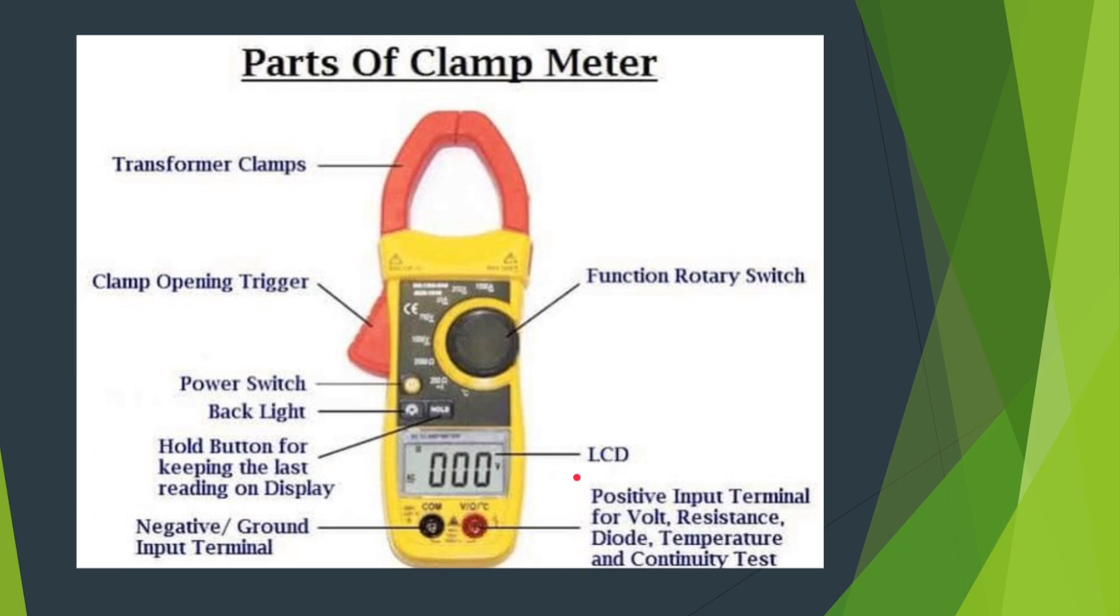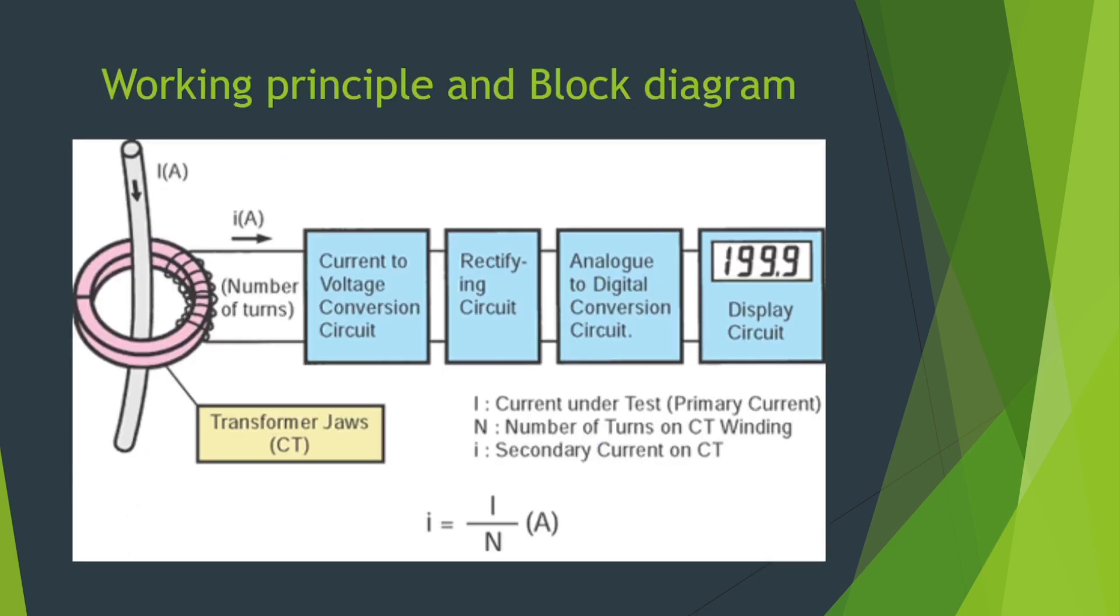LCD display is used to show the measurements. Function rotary switch enables the user to select different measurement modes. Let's understand the working principle using this block diagram. In general, AC clamp meters operate on the principle of current transformer which is used to pick up magnetic flux generated as a result of current flowing through a conductor. Assuming a current flowing through a conductor to be primary current, you can obtain a current proportional to the primary current by electromagnetic induction from the secondary side of the transformer which is connected to a measuring circuit of the instrument. This permits you to take an AC reading on the digital display as illustrated by the block diagram. The formula given here can be used to calculate the current.